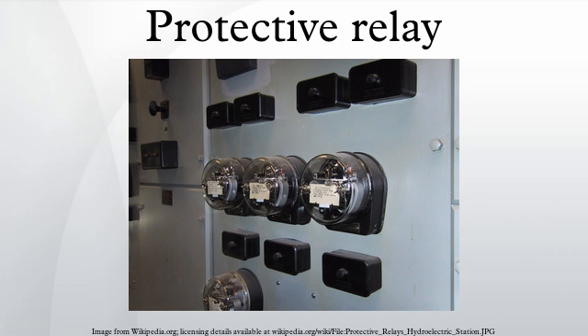This relationship of eddy currents and fluxes creates torque proportional to the input current of the primary winding, due to the two flux paths being out of phase by 90 degrees. In an overcurrent condition, a value of current will be reached that overcomes the control spring pressure on the spindle and the braking magnet, causing the metal disk to rotate towards the fixed contact. This initial movement of the disk is also held off to a critical positive value of current by small slots that are often cut into the side of the disk.